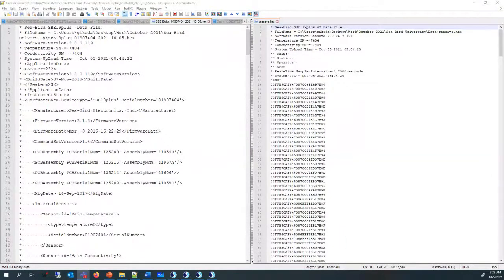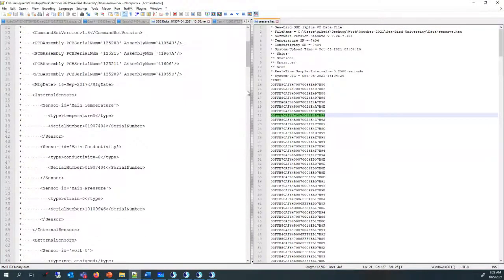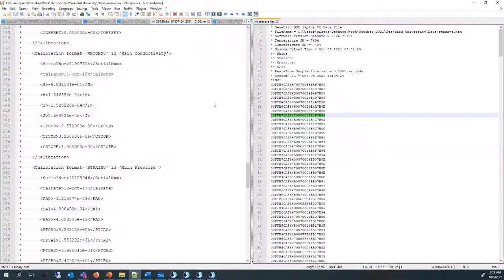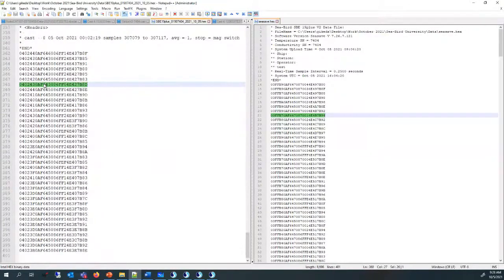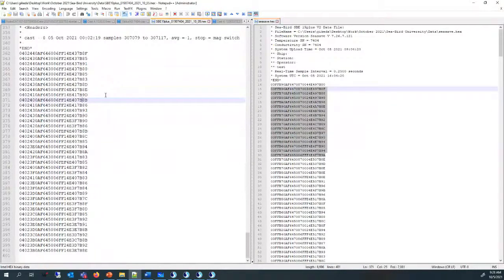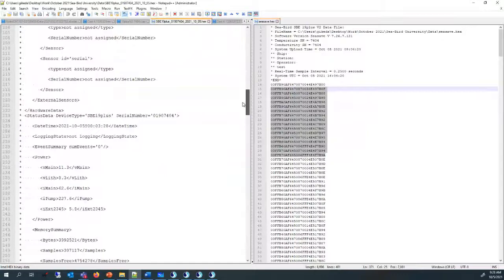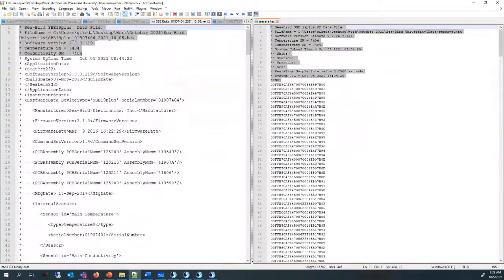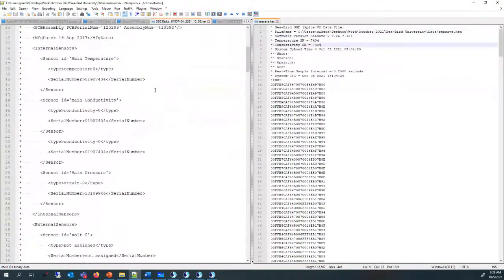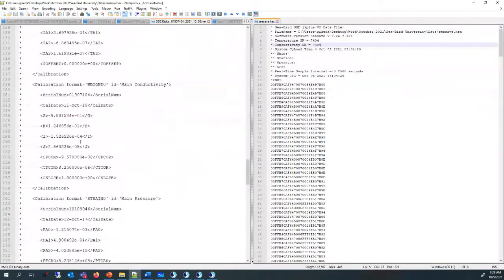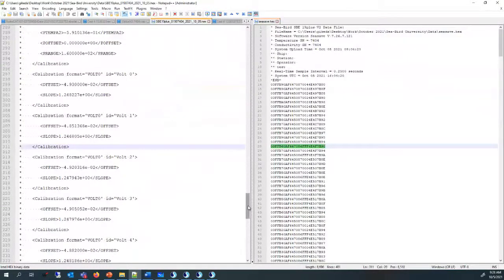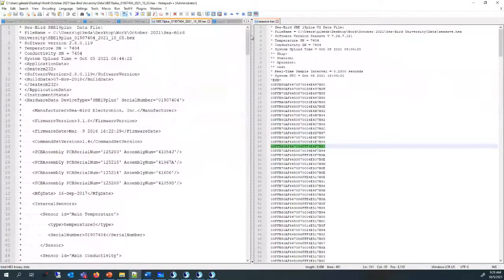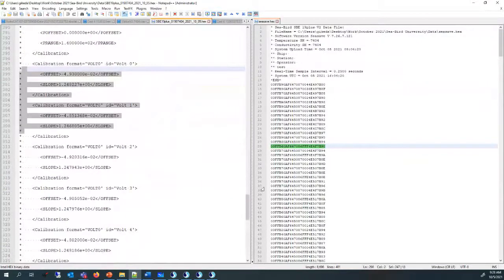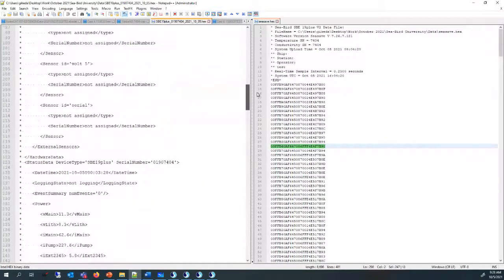One thing I want to add to that is the data format is the same as what you collect live in Seasave, this hexadecimal format. I think these are two different casts, but it's a good example. Say this is a hex file that we uploaded from the memory from a cast we did, and this is a hex file that was written by Seasave. The data you have here is going to be the same. However, the header is going to be much more verbose from the data you upload from the CTD versus what's written in Seasave. Seasave isn't doing this automatic thing where it's sending all the status commands and writing those to the header of the file, but it is collecting the data. Seaterm, when you upload data, is going to do that. So this provides a lot of useful information about the calibration coefficients on the CTD and the configuration of the CTD. That's useful for troubleshooting in the future or just keeping a record of your instrument.